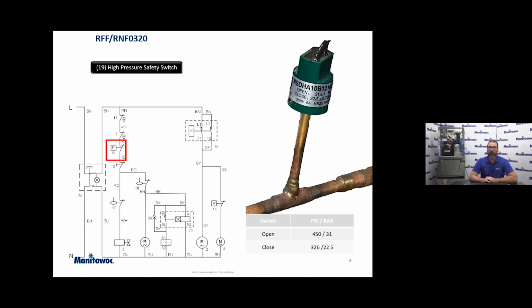They're in bar here, but a simple conversion on your smartphone or computer, laptop, what have you, a simple converter can get you where you need to be if they're not in PSI, which most of us here stateside are used to using. So the key takeaway from this is be wary of the machine you're working on. If you're testing this switch, there are going to be different cut-in and cut-out pressures for either a fan cycling switch, high pressure cutout, even a low pressure cutout. It's going to be based on the machine itself. So don't take for granted that if you know one, they're all the same.